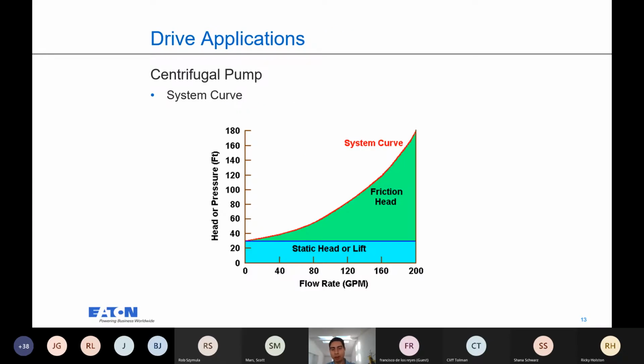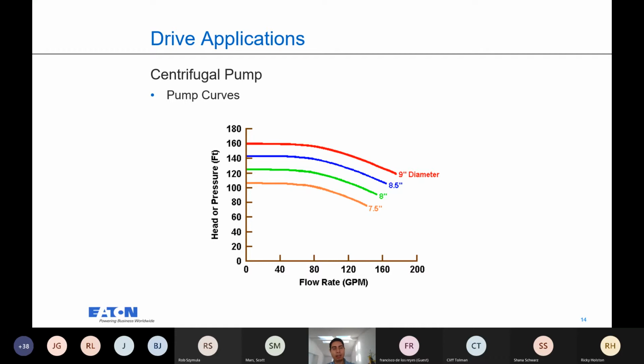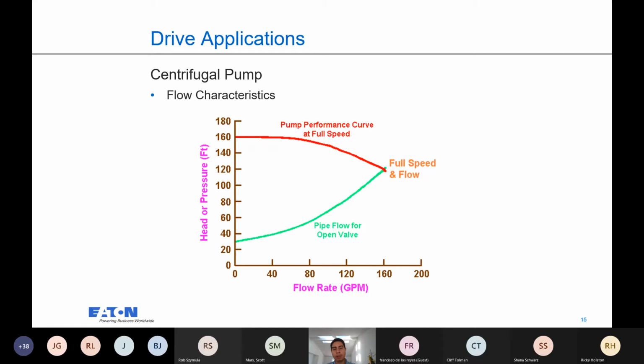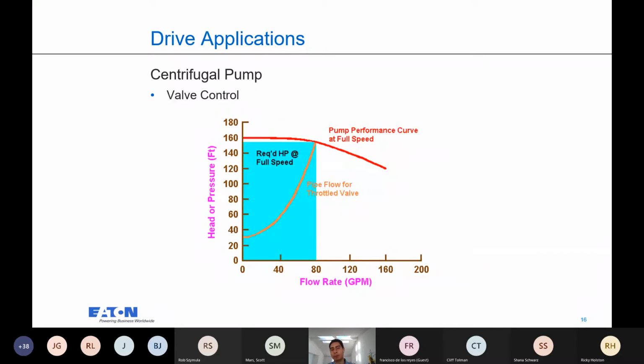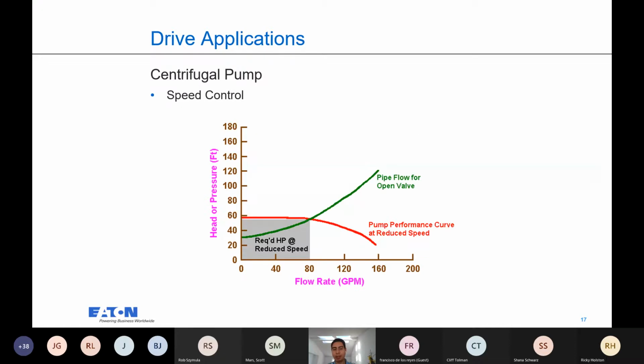So if you're looking here, your static head versus your friction head and your system curve, let's compare that 1-to-1. So here are a few examples of pump curves and the flow rate that you need to go to be able to overcome the system flow. So if you go with a full speed at a higher head, here's your curve here, your system curve and your pump curve. But if, let's say, we require reduced speed and we use a valve, we still have a high head of pressure to overcome, and then compare that to a head using a variable frequency drive. So your head significantly was reduced by you just reducing the speed and a VFD.